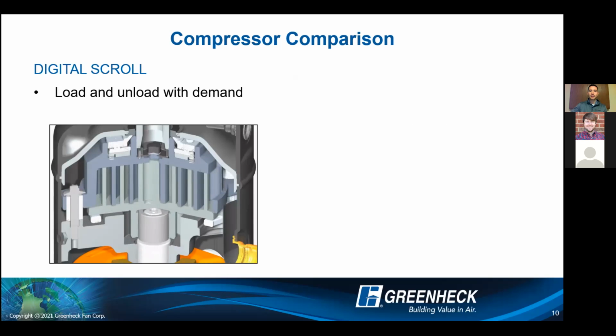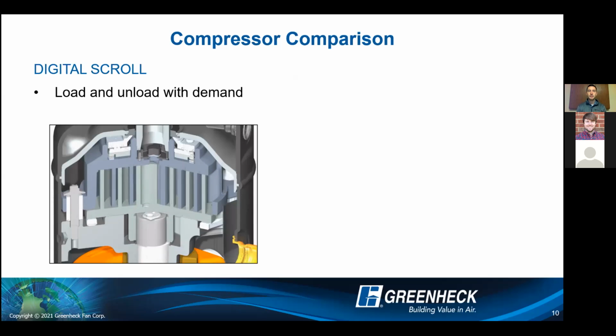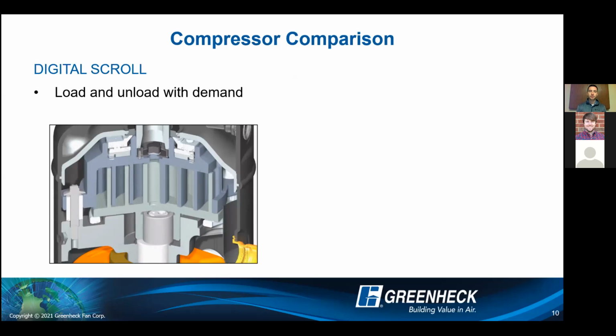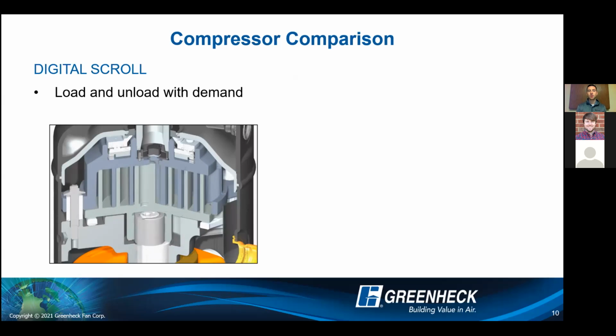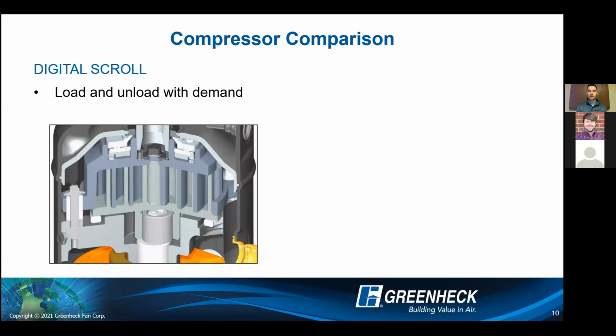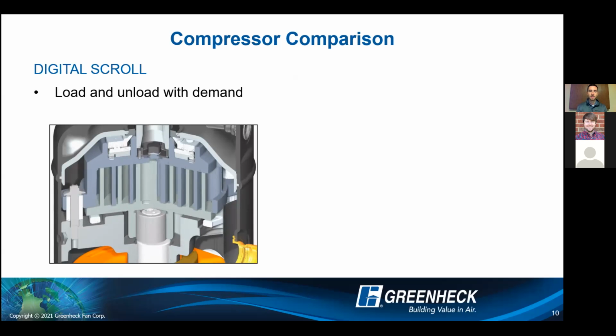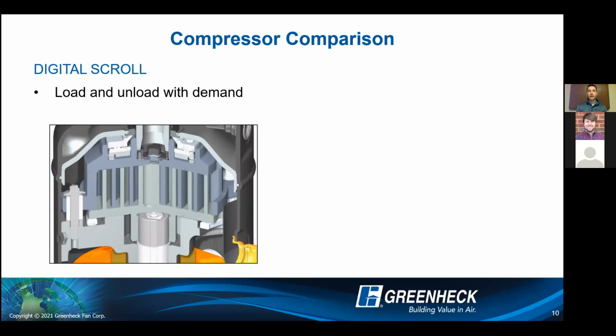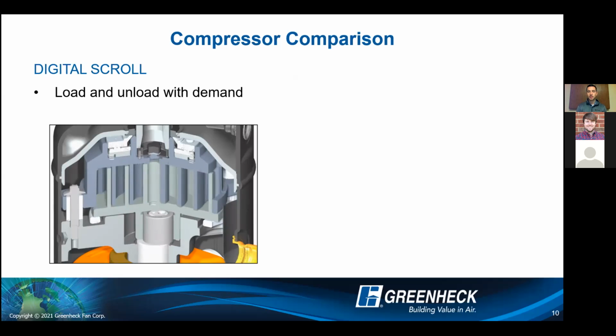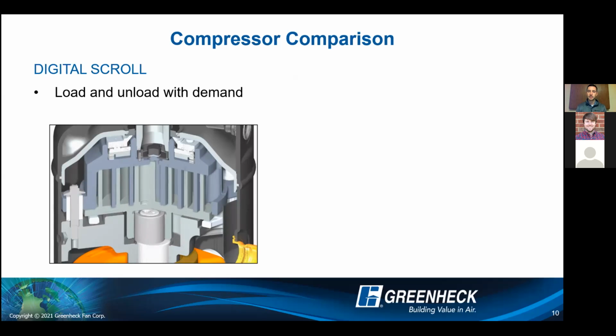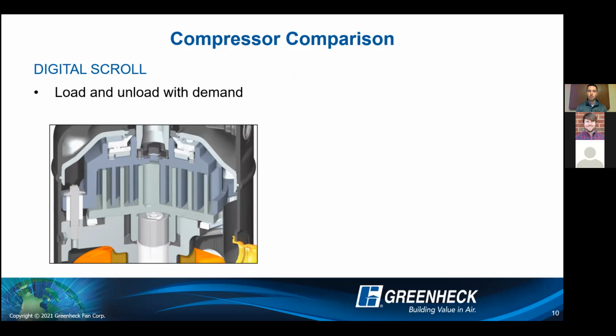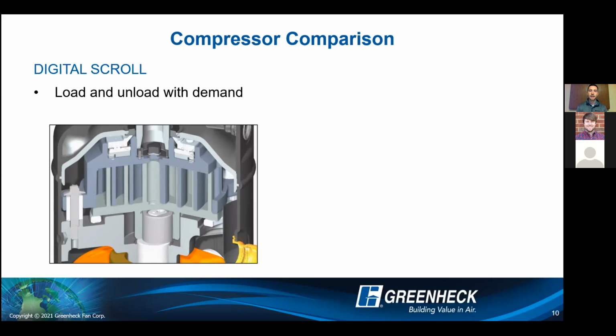So now I want to look at the compressor comparisons related again to cooling and efficiencies. So first one is going to be the digital scroll. And this is really loading and unloading based off of demand. And when I say loading and unloading, it is almost like a mechanical clutch in a vehicle. What digital scrolls actually do is they have a really good ability to modulate to capacity. So you still get that tight temperature control, but it's looking at a 15-second window.